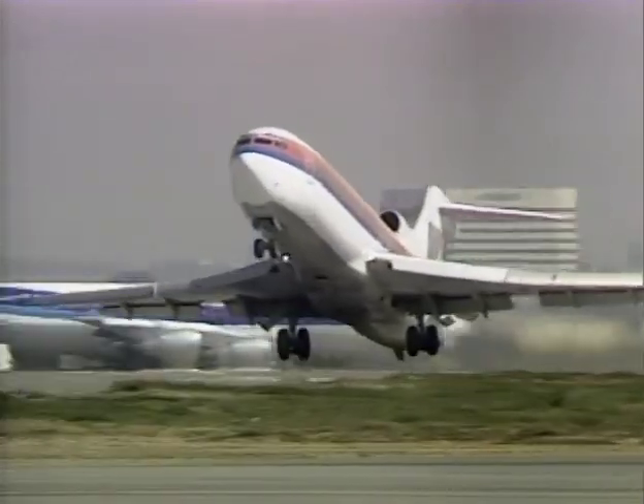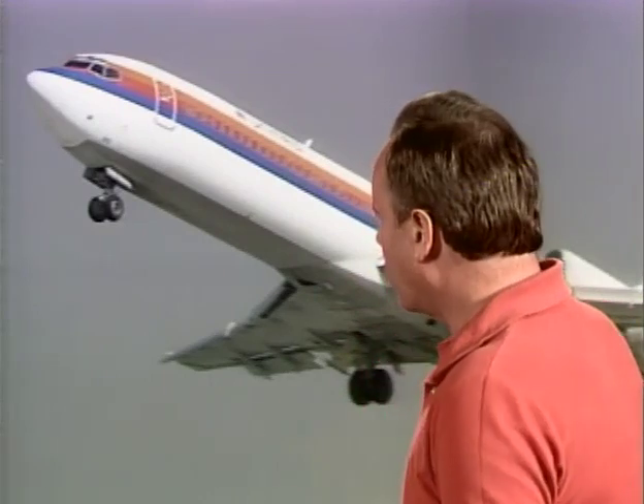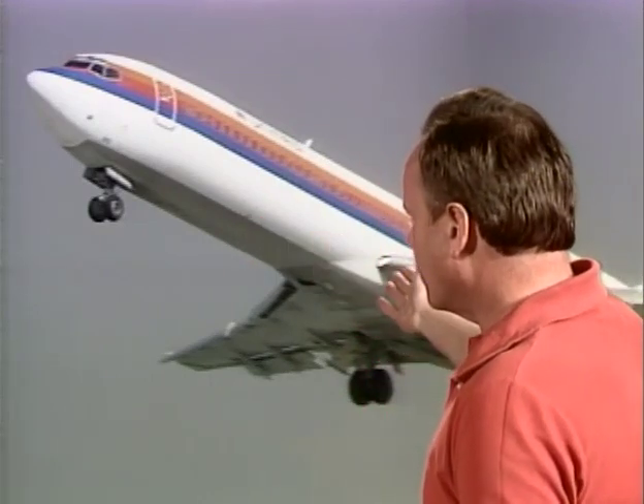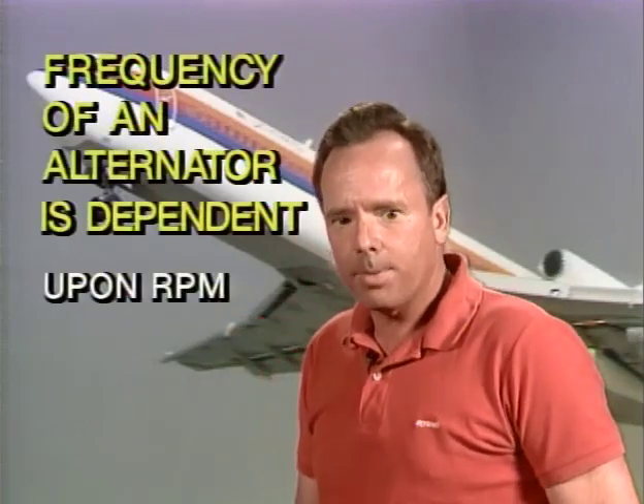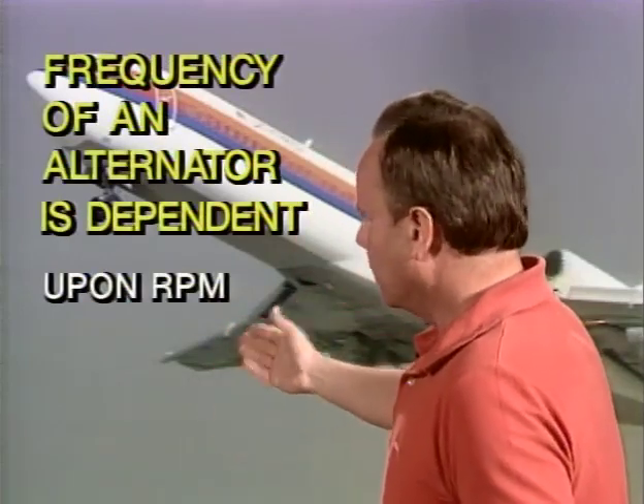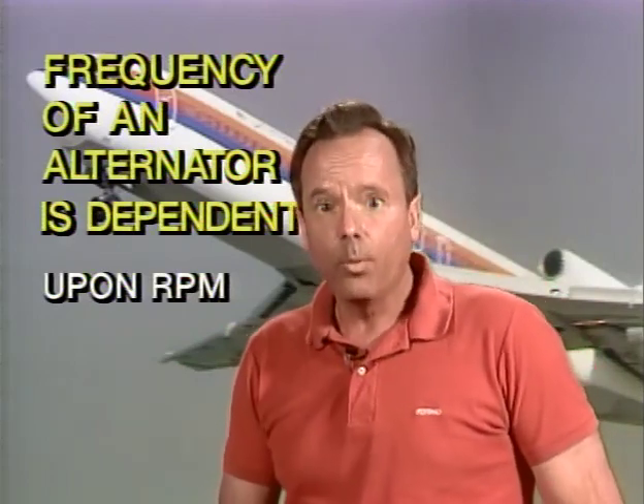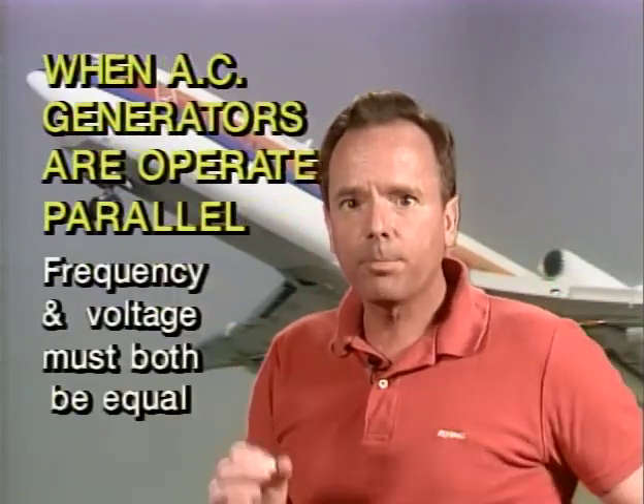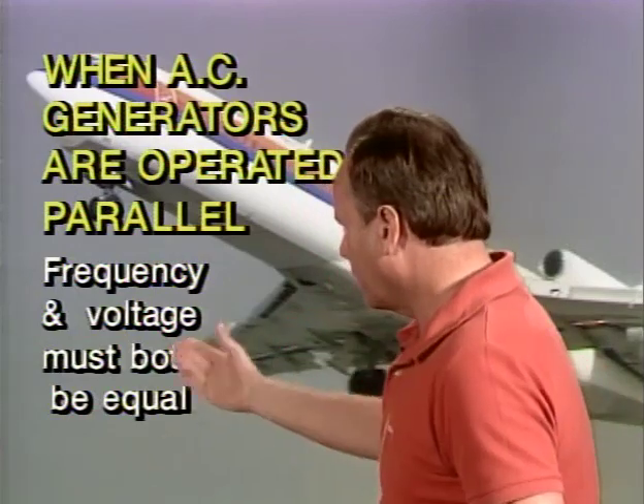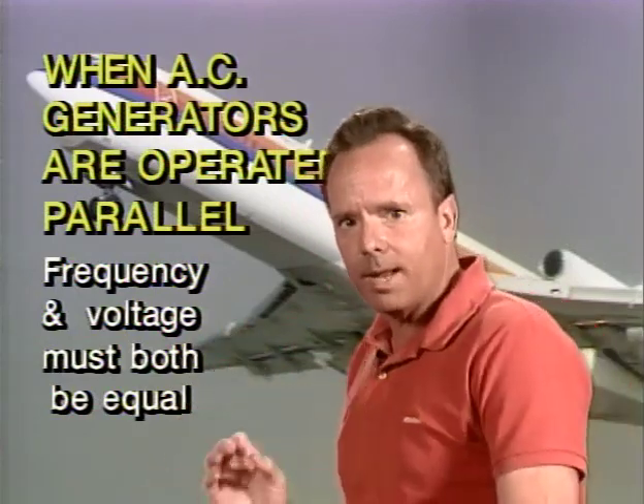Now big airplanes like this Boeing 727 have, instead of DC generators, alternators, or alternating current generators they're called, but they produce alternating current. Now paralleling alternators or AC generators is an entirely different kind of thing. You have two things to take into consideration: voltage and frequency. Now the frequency of an alternator is dependent upon RPM. The faster it turns, the higher the frequency. Now when AC generators are to be operated parallel, then the frequency and voltage both must be equal. You got to keep both of them equal.